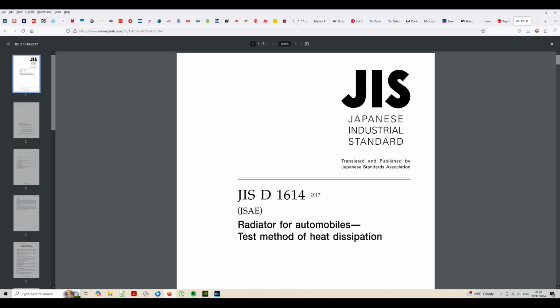Now that we've covered the test subjects, we're going to look at the test standard. We're going to be referencing and using JIS D 1614 from 2017 as our procedure. As you can see, it covers automobiles but should work equally fine for these 3 radiators. Being that these JIS standards are under copyright, unfortunately this is about as much as I can show you of these papers. However, this is the formula that we'll be using. As you can see, we've got several points of data that will be logged during the test, which we'll then input into this spreadsheet to give our heat dissipation in kilowatts.